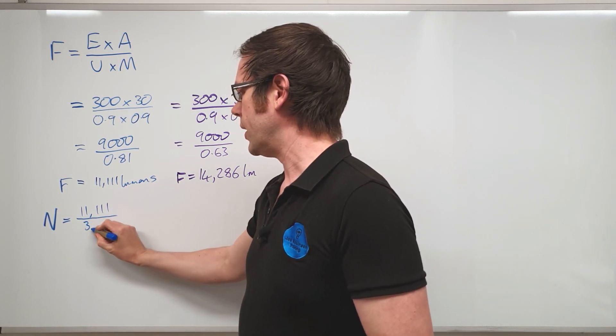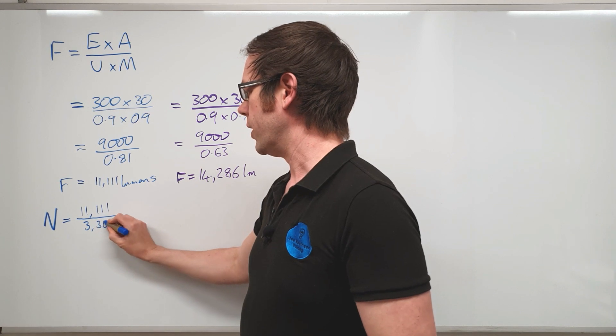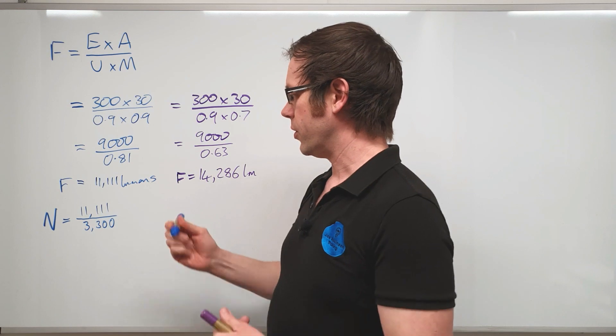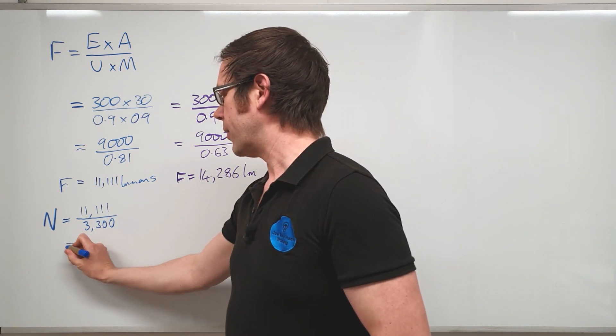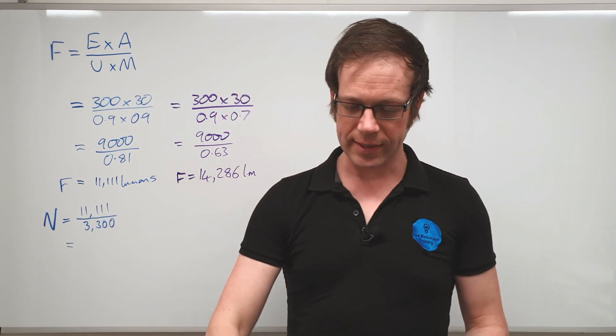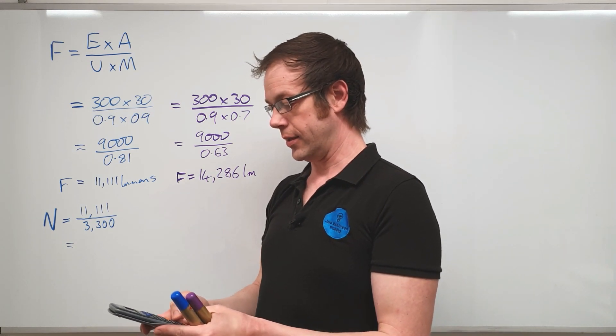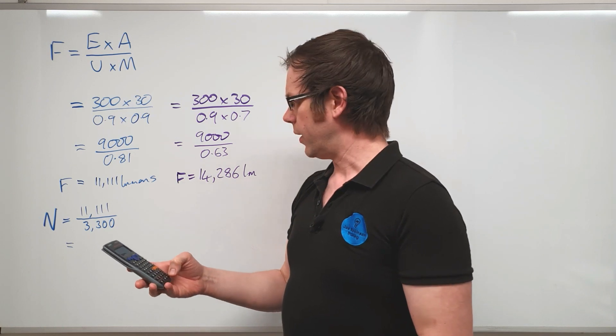So let me show you what I mean. We're trying to find what is often given the letter N as a capital for number of fittings. All we've got to do is take our required lumen level of 11,111 and divide it by the lumen output of the light fitting.